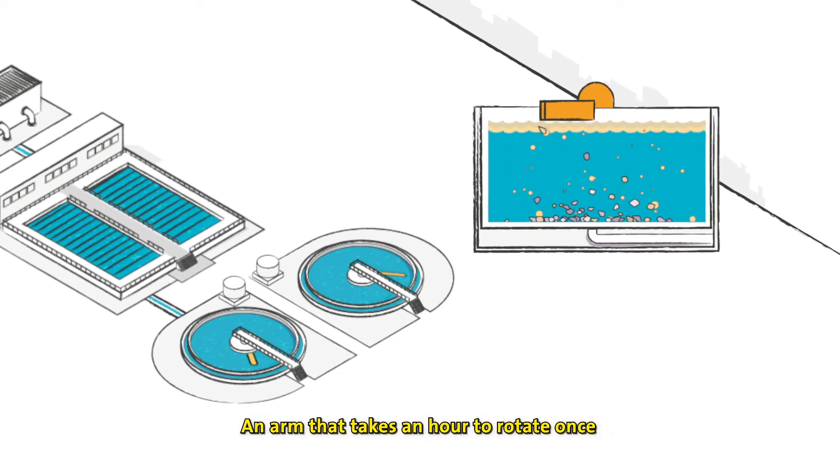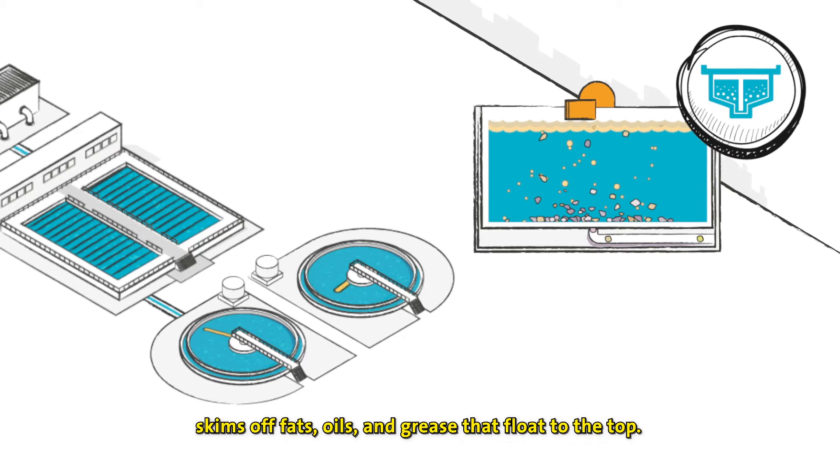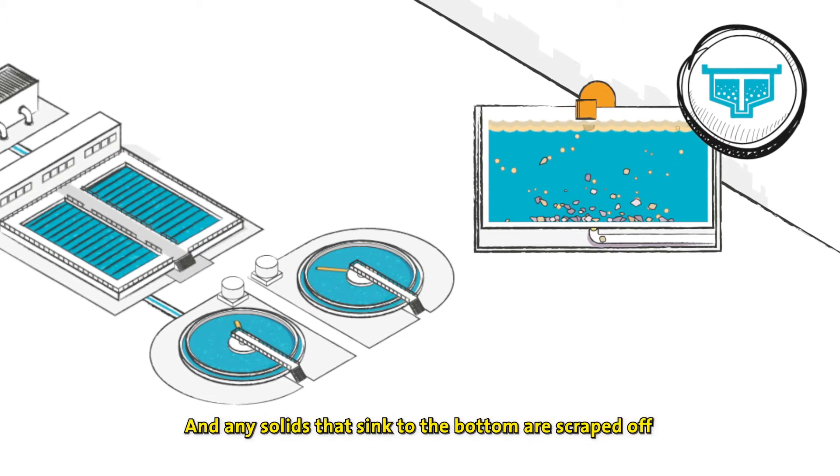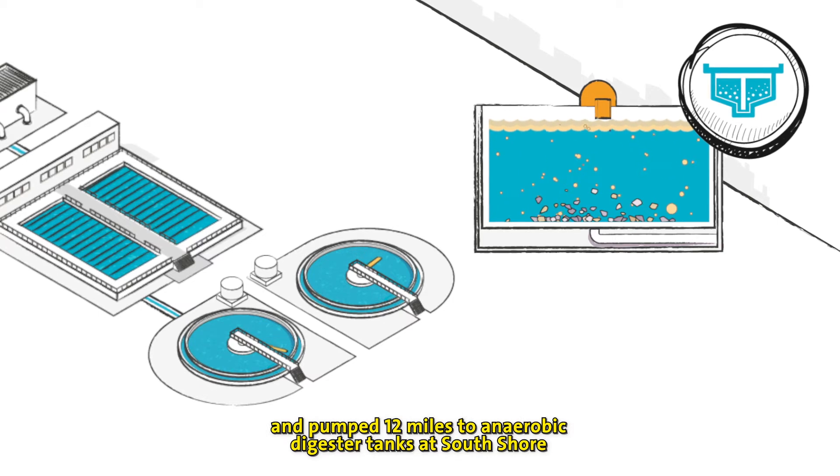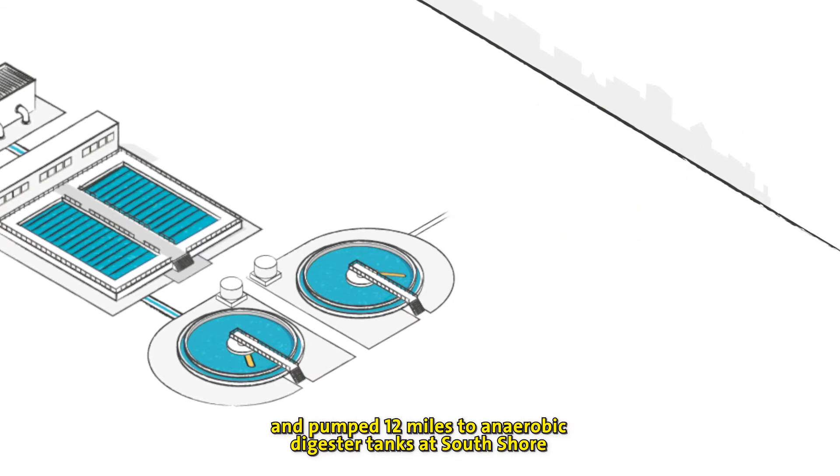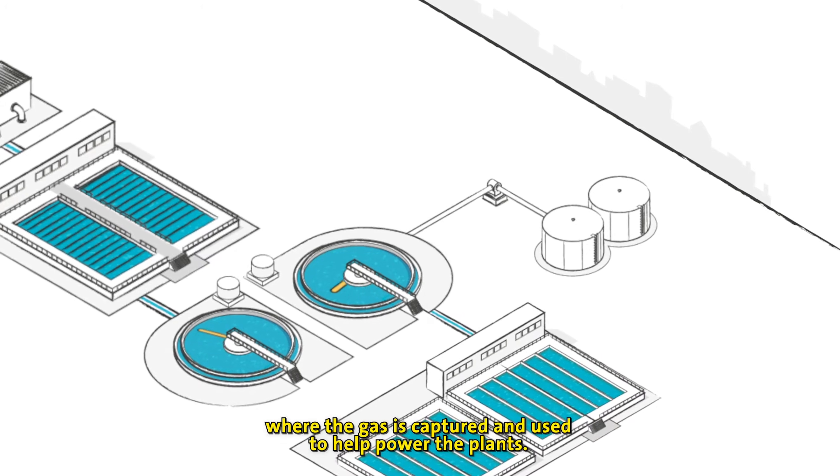An arm that takes an hour to rotate once skims off fats, oils and grease that float to the top, and any solids that sink to the bottom are scraped off and pumped 12 miles to anaerobic digester tanks at South Shore, where the gas is captured and used to help power the plants.